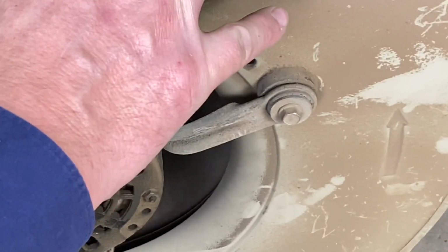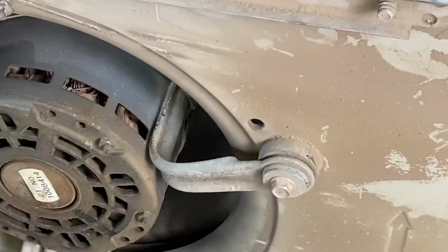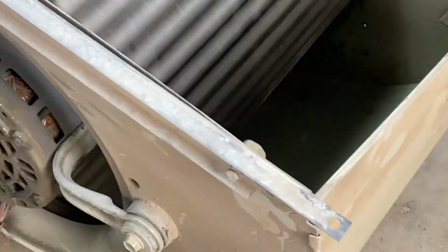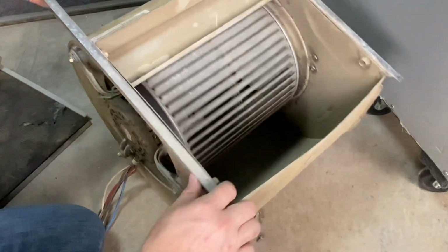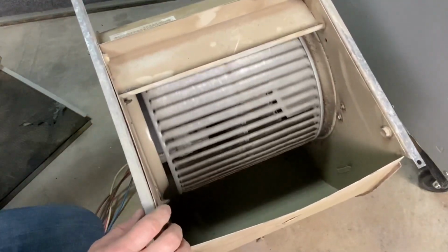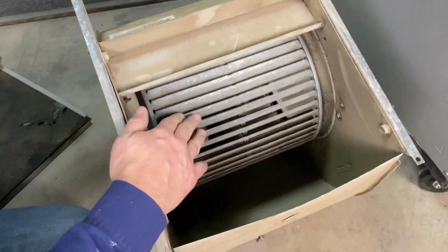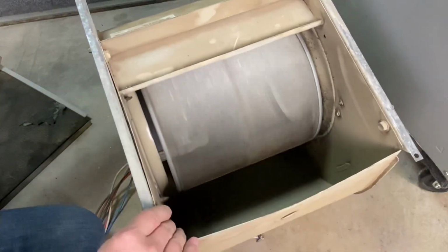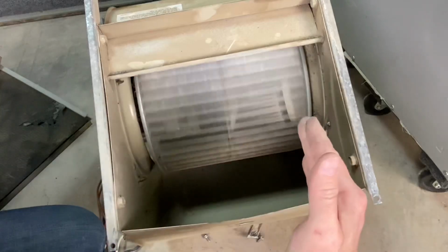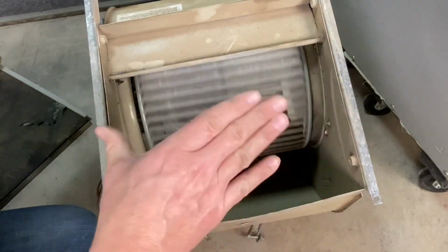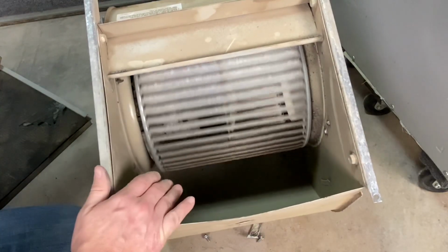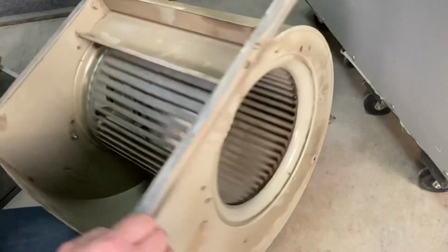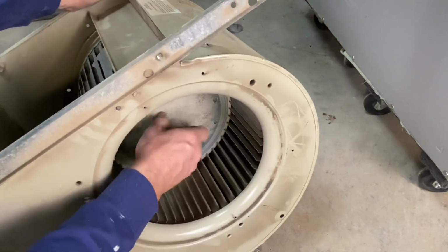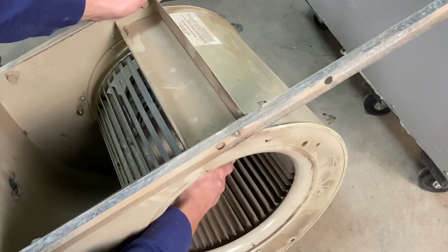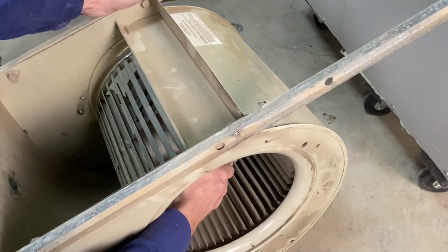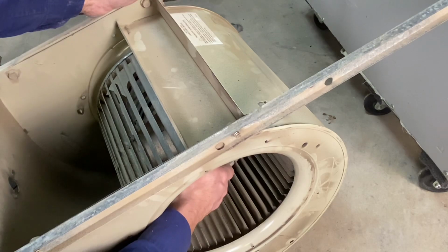We can also check the bearings, see how well the wheel moves. This wheel is moving pretty smooth, which is a good sign. Notice it's still spinning. It's going to come to a nice slow stop. That's one thing we look for. We also look to see, as we're turning this, that the blades are nice and smooth. Sometimes you'll see this thing wobble back and forth, and that's telling you you have an issue with your blower wheel. Another thing I want to look for is I grab the hub of this motor and try to move it up and down to see if there's any play in it. And there's just a little bit of play in the bearings.